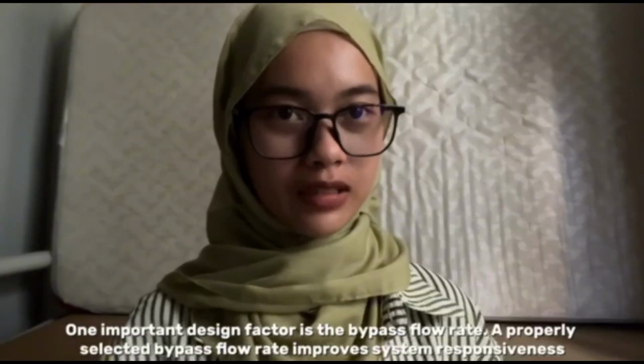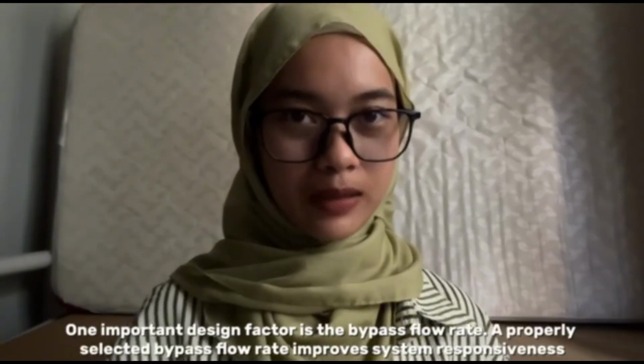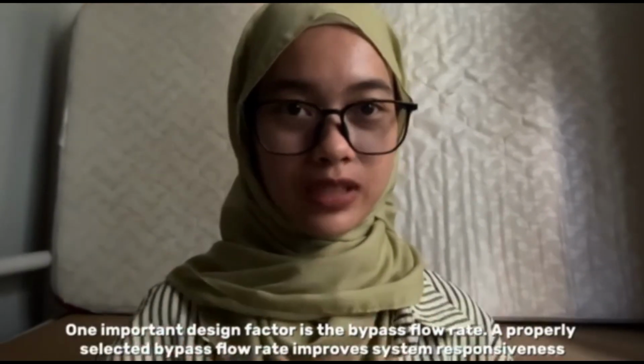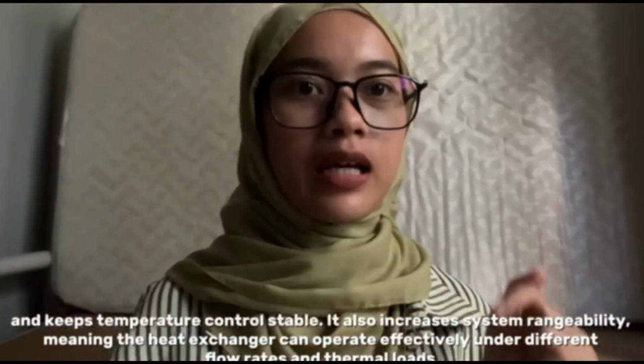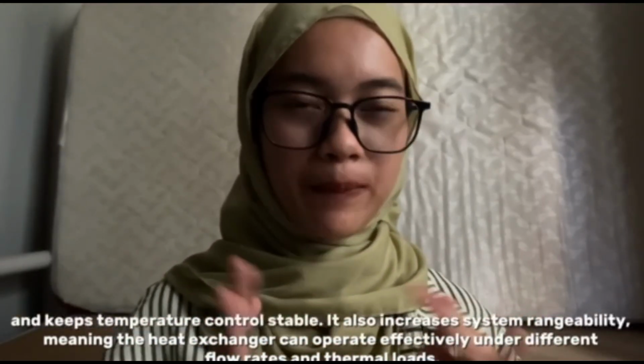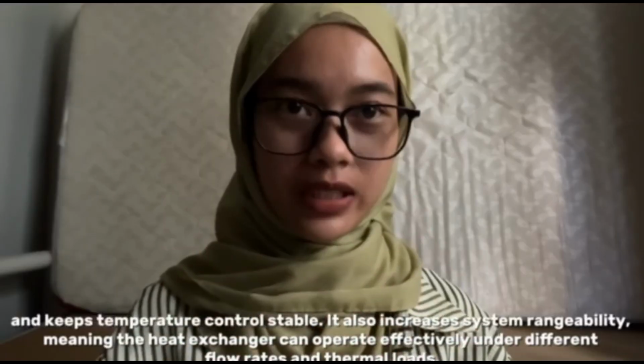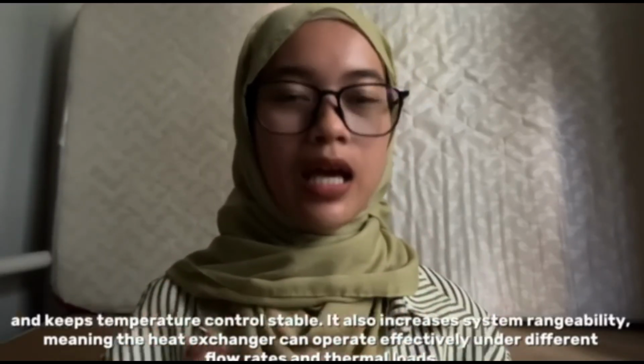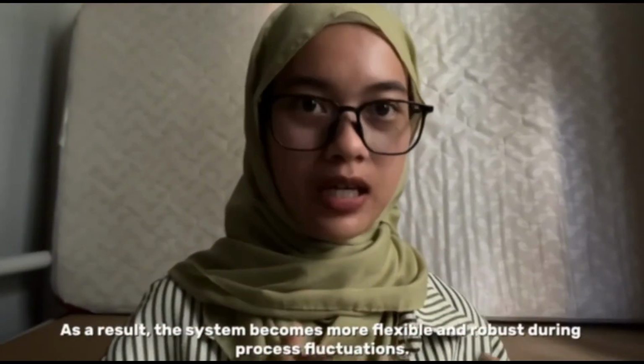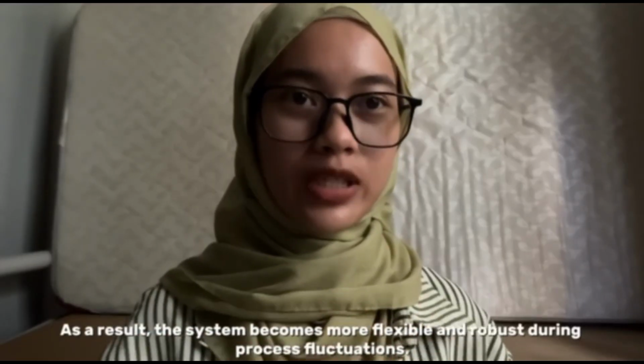One important design factor is the bypass flow rate. A properly selected bypass flow rate improves system responsiveness and keeps temperature control stable. It also increases system rangeability, meaning the heat exchanger can operate effectively under different flow rates and thermal loads. As a result, the system becomes more flexible and robust during process fluctuation.